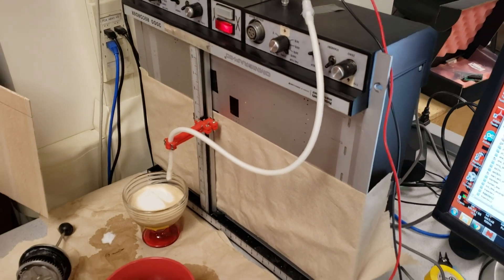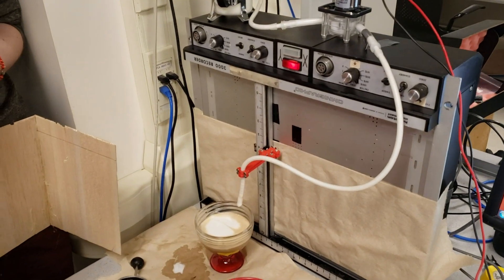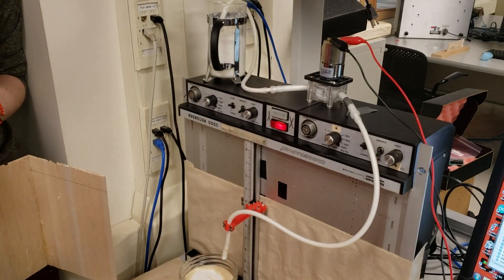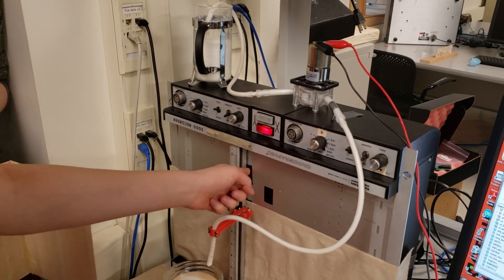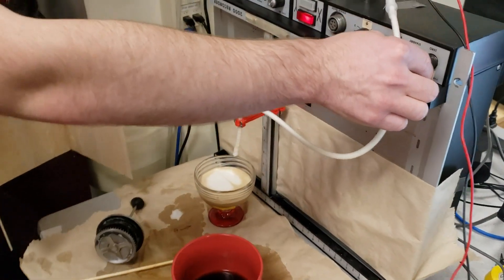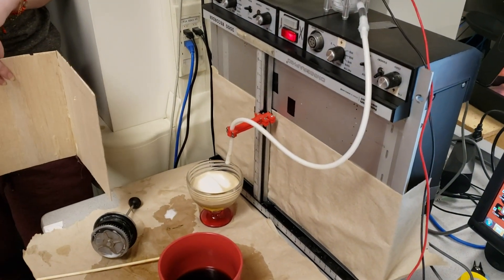When you're doing setup, do you position this manually or are there controls for positioning from the PIC? There really is no controlling from the PIC in terms of initial positioning — we just marked it so that we always start in the same place. Then you can do a little bit of amplitude adjustment on the side to do fine tuning for the design.